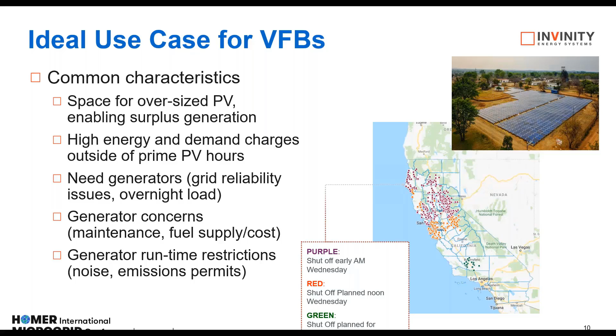But there are some factors that specifically favor the use of vanadium flow batteries in your projects. One of these is the need for frequent and deep cycling. If you're seeing a project that is indicating a need for the battery to cycle more than 300 times a year for over 2 hours each, or 600 cycles a year at less than 2 hours, and in particular, if the model is seeing the need to discharge the battery down to 100% depth of discharge, this is when you want to start looking at a vanadium flow battery, due to its very low degradation and its ability to run at that very deep level of cycling without any effect on the warranty.